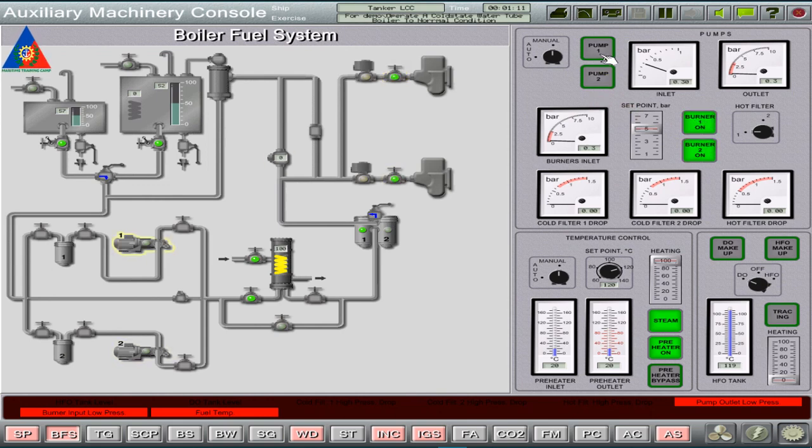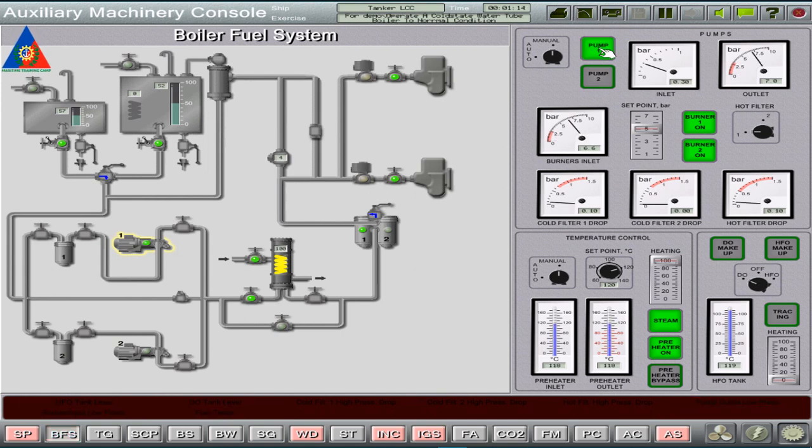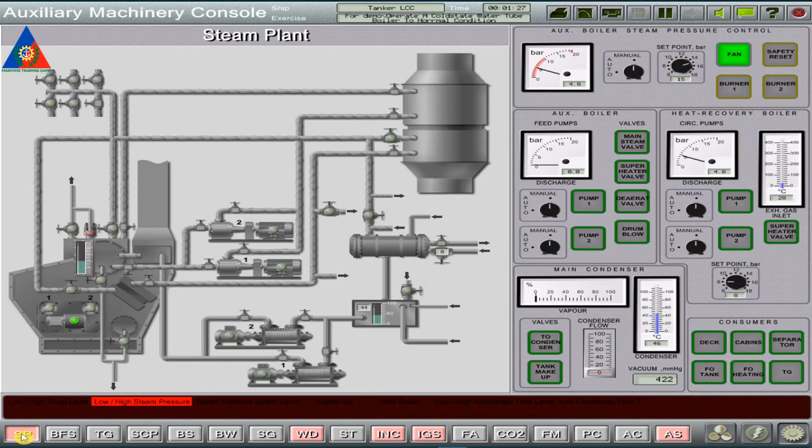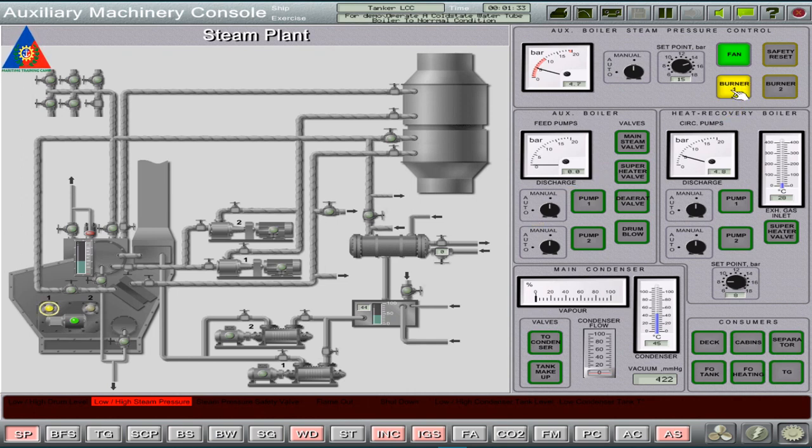After which, turn on feed pump number 1 and set it to auto-running mode. If the pressure readings are normal, go back to the SP page and manually fire or turn on burners number 1 and number 2.